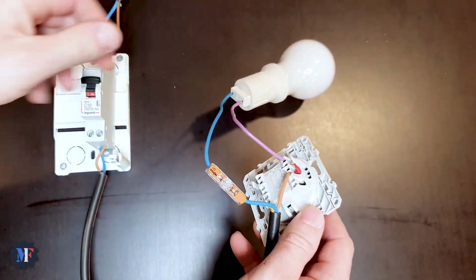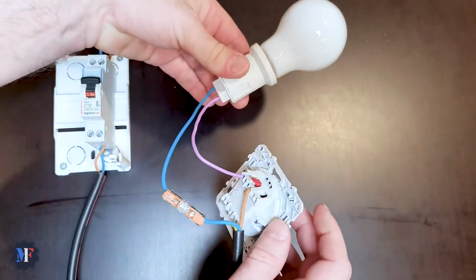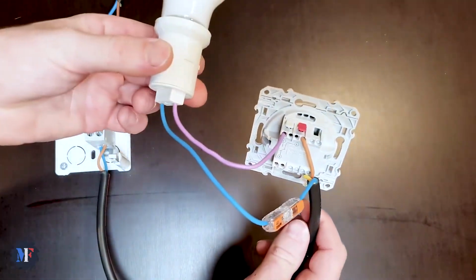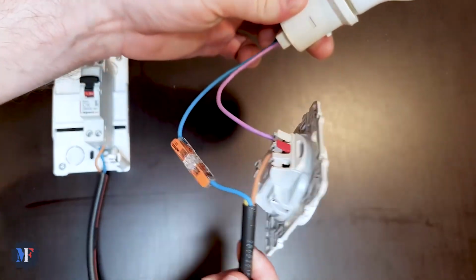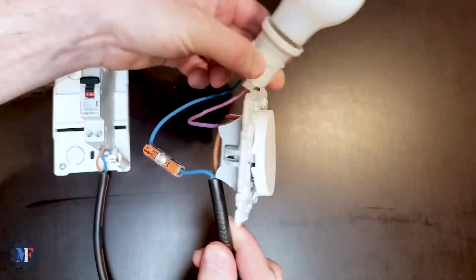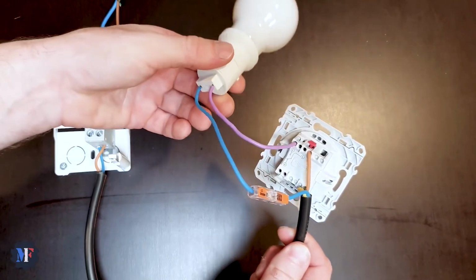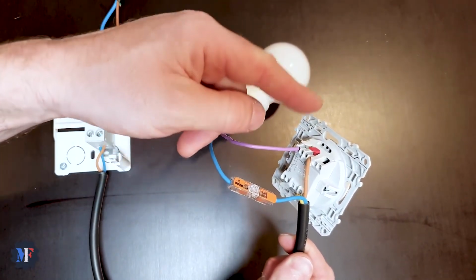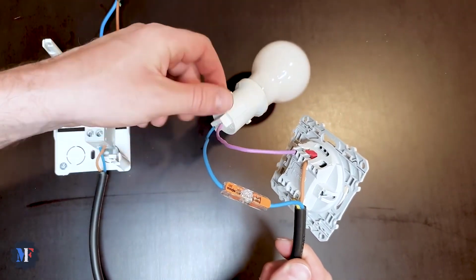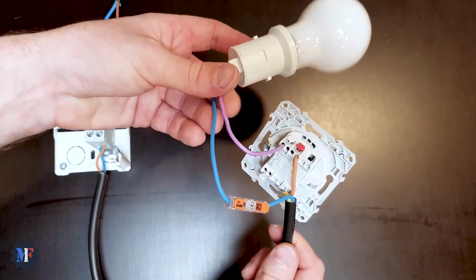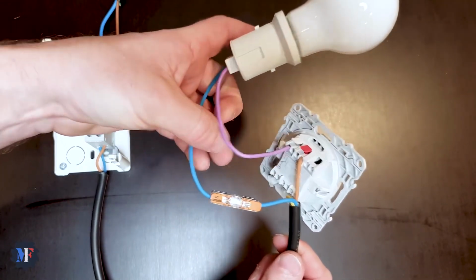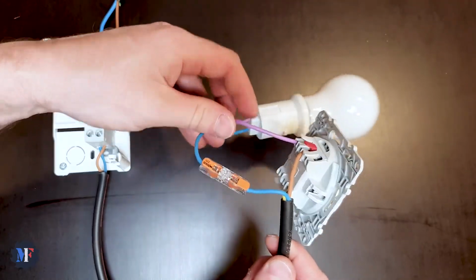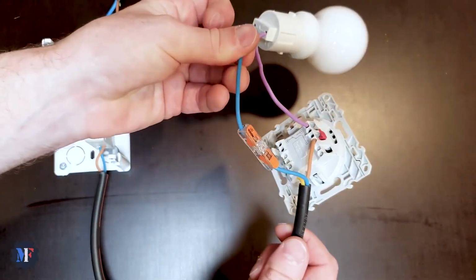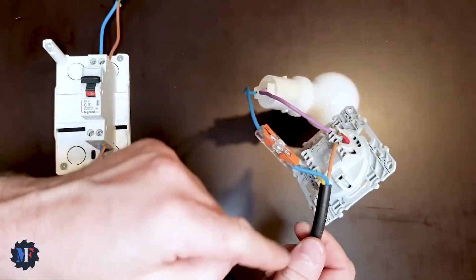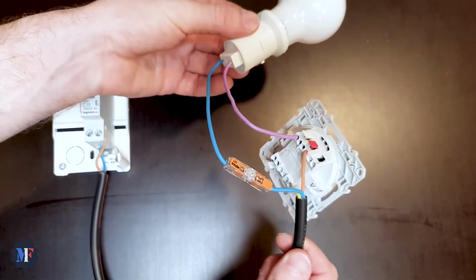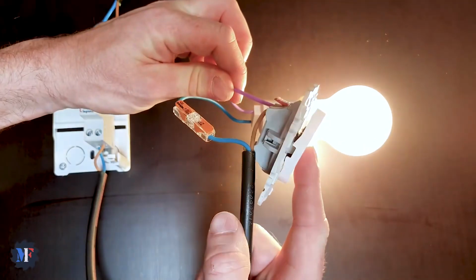There we go, we put it back, and it works, so that's it. It should look like the wired switch, nothing complicated, except that when you go from the switch to the bulb, you run another wire of a different color. It could be red, orange, or purple, here you see purple, so use whatever color you want. But as I was saying, the blue wire stays blue, connected directly from the 10 amp breaker to the bulb, and we switch the hot wire.